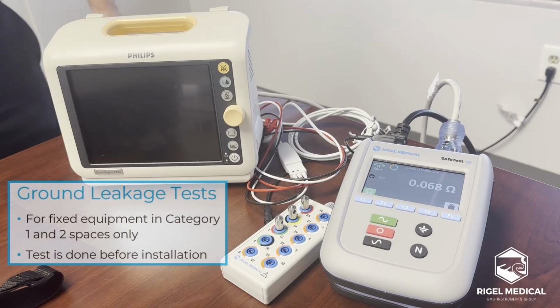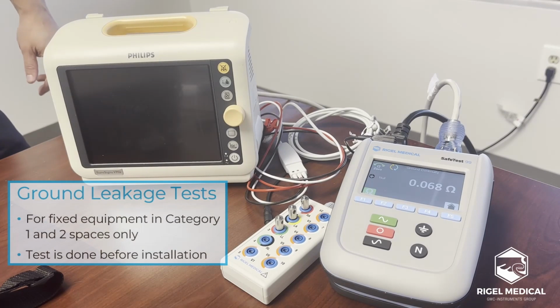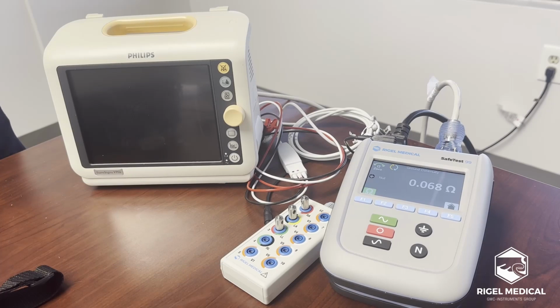So if I scroll down through the presentation, first we've got leakage current tests. That's ground leakage, touch leakage, and patient leakage. Ground leakage is for fixed equipment in category 1 and 2 spaces only. So this isn't fixed equipment, it's a portable device. So we don't need to perform that test. Very rarely would you be performing a ground leakage test.